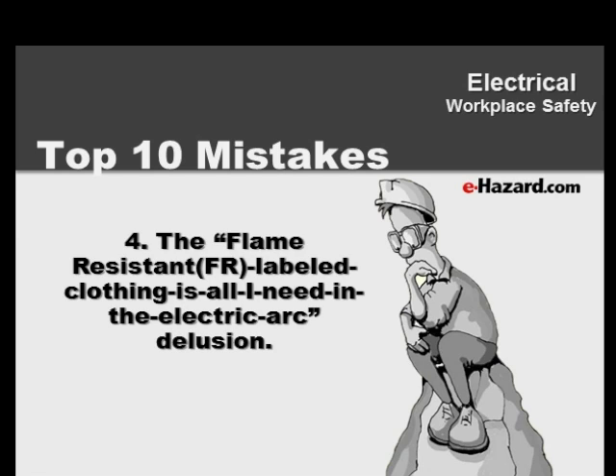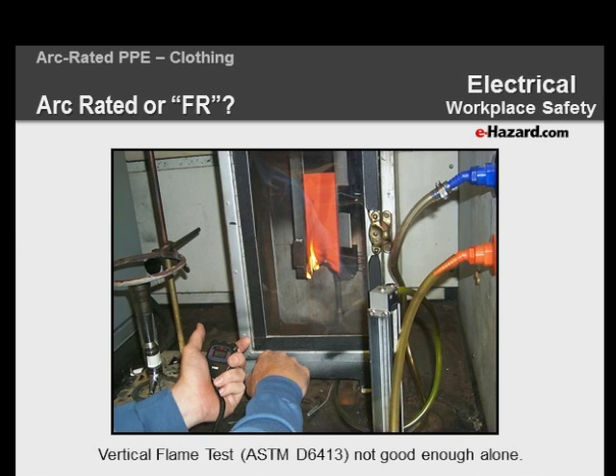This is really important. We see a lot of things in the market, especially specialty garments like hoods and things like that, that actually aren't arc rated. They don't have the right labeling, and they say they're flame resistant. Well, what they mean is that we've done a vertical flame test and it went out at whatever length we've set—some say 4 inches, some say 6 inches. This vertical flame test is a great control device, a great control standard, but it doesn't mean that something will actually work in your hazard—in this case, electric arc. You really need to make sure you're matching it to the hazard, and that means getting arc-rated gear that has the right arc rating for the exposure you have.